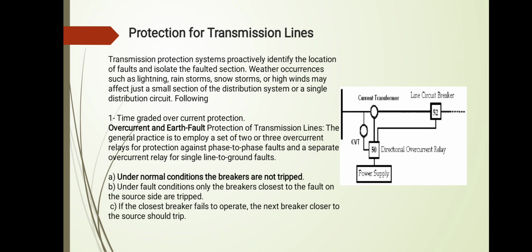What should we do to protect the transmission line? Transmission protection systems identify the location of faults and isolate the faulted section, weather occurrences affect just a small section of the distribution system or a single distribution circuit. The following is time graded overcurrent protection, overcurrent and earth fault protection of transmission lines. The general practice is to employ a set of 2 or 3 overcurrent relays, as illustrated in the figure, to protect against phase-to-phase faults, and a separate overcurrent relay for single line to ground faults.